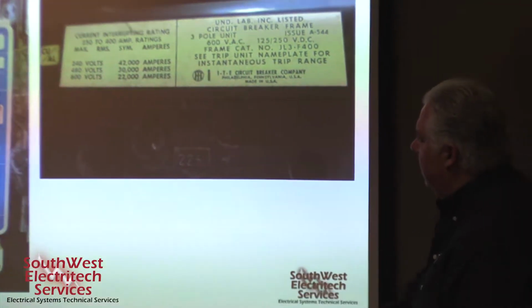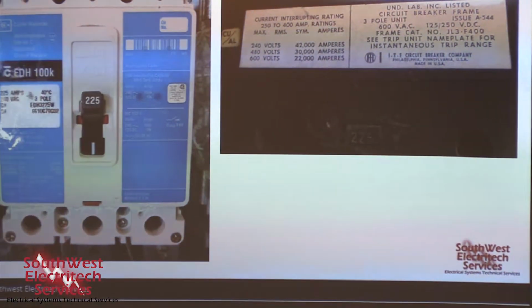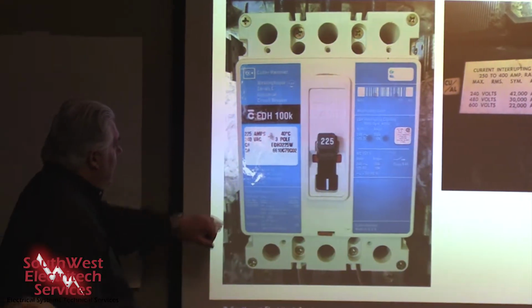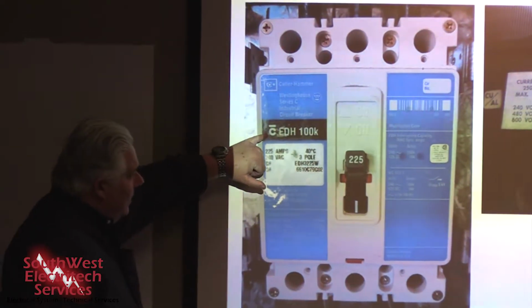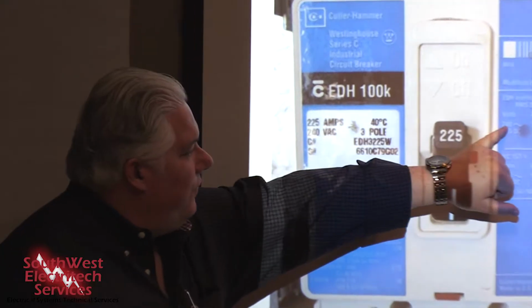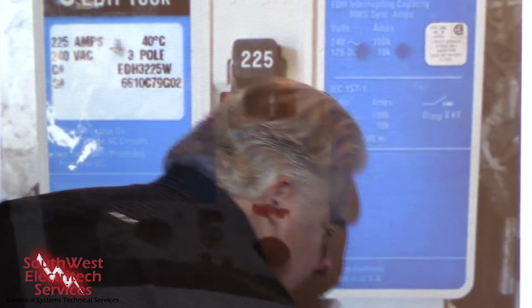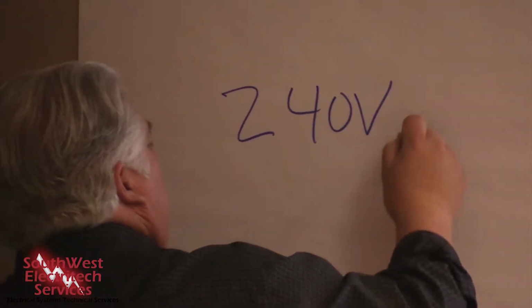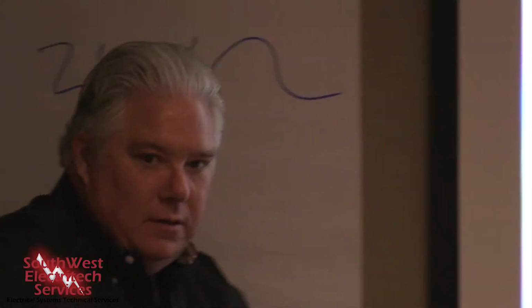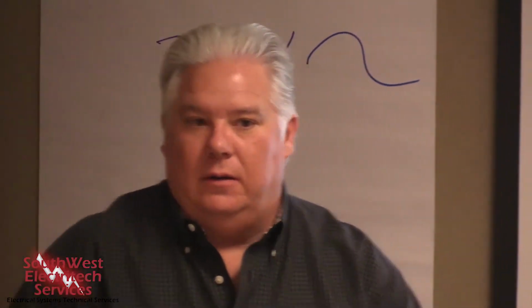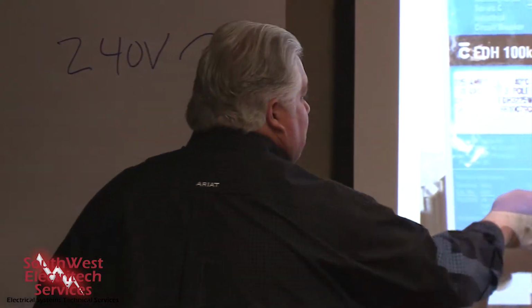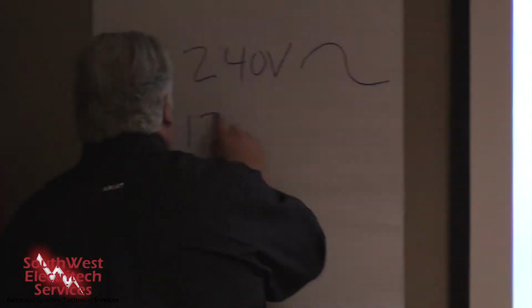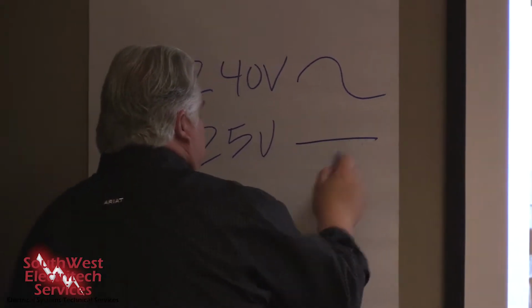Now let's look at this breaker, and it's got a little scar up on its nameplate a little bit. But this particular breaker is rated for 100K at 240 volt, and there's a squiggly line. So it's rated at 240 volt, and it's got this. What does that mean? Alternating current. AC current. Exactly right. It also has another rating on it. It says 125 volt, and it has a straight line.